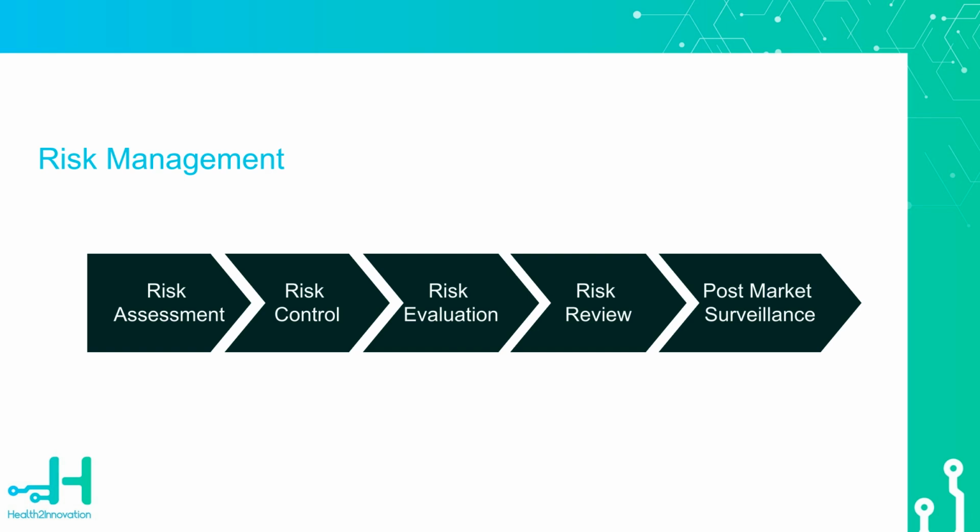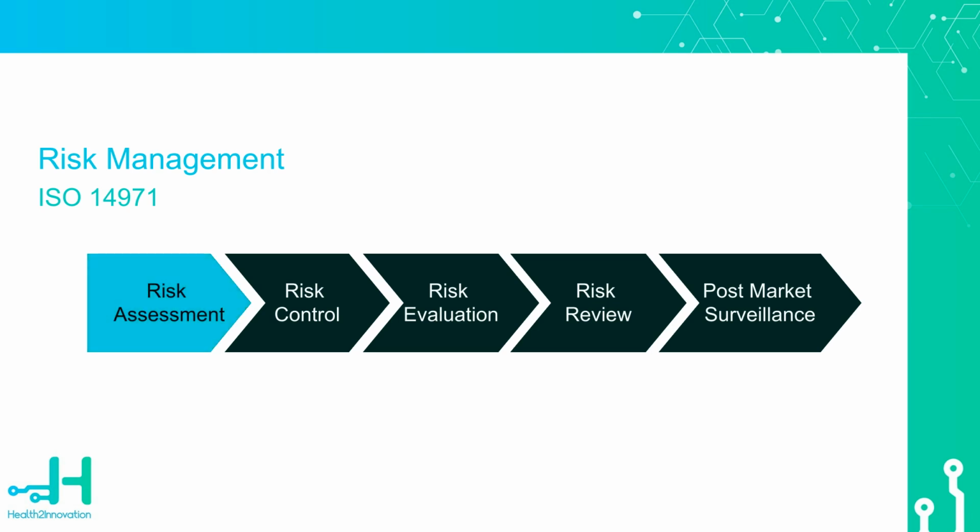This system must be integrated into the manufacturer's quality management system, our QMS, and continuously updated throughout the device's lifecycle, including post-market surveillance. ISO 14971 is the international standard that provides a framework for risk management specific to medical devices. It outlines the steps necessary to identify hazards, estimate and evaluate risks, control these risks, and monitor the effectiveness of the controls. In risk assessment, we use available information on our own or previous or similar devices to identify characteristics associated with safety or harmful conditions.